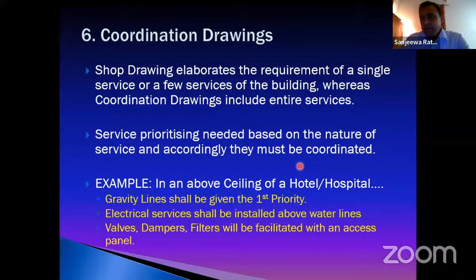When preparing coordination drawings, normally the gravity lines need priority. It's also understood that electrical services shall be installed above water lines if present. Then valves, dampers, and filters should be provided with an access panel.